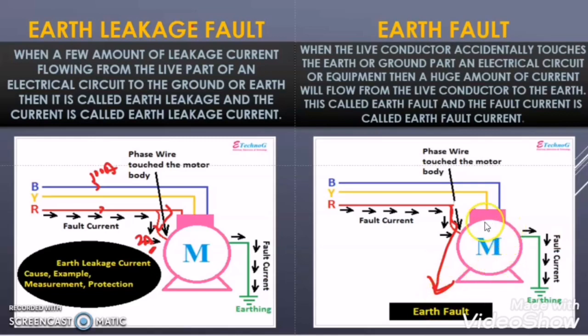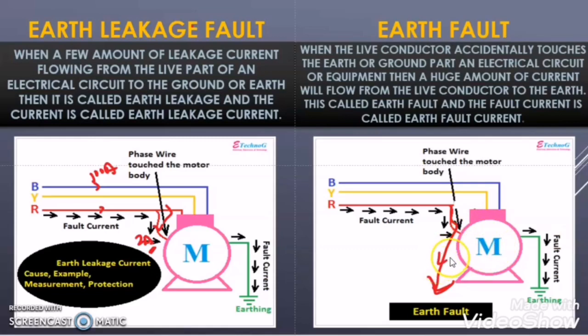Then what happened in this situation? There is a phase loss in the motor. Before, there was 100 Ampere of current flowing through the R winding of the motor in healthy condition. But when something happens in the R phase, then there will be zero current flowing in the R winding of the motor and all the current is flowing now to the ground. So such a condition of fault is called earth fault condition.